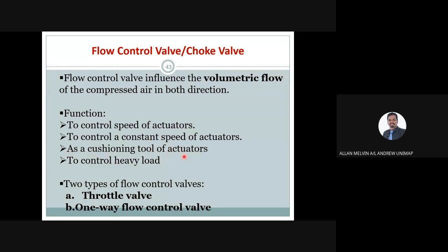The second function of a flow control valve is to maintain a constant speed even if supply pressure is uneven — regulating the speed so it remains always the same to the actuators, which helps the actuators last longer. A third function is as a cushioning tool: using compressed air to provide a cushion for the cylinder, so when the piston reaches the end of its stroke it slows down, reducing impact.